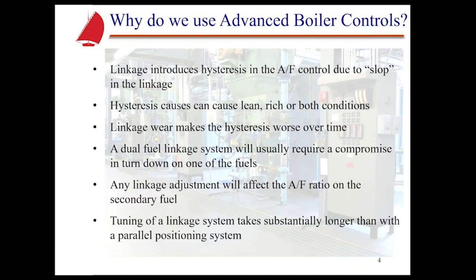Well, truth of the matter is, linkage systems introduce hysteresis in the air-fuel ratio control due to slop in the linkage. And even though there are many, many different types of linkage designs out there from the different burner manufacturers, it's always a compromise because of that linkage. Hysteresis can really cause a lean condition, a rich condition, or both conditions. So actually, when we're going up the firing rate, going from like low fire to high fire, we could actually be in a lean situation. And then as we start coming back down in firing rate, we could actually go rich. And that is, of course, not ideal.